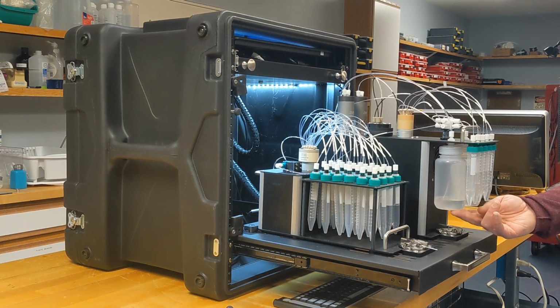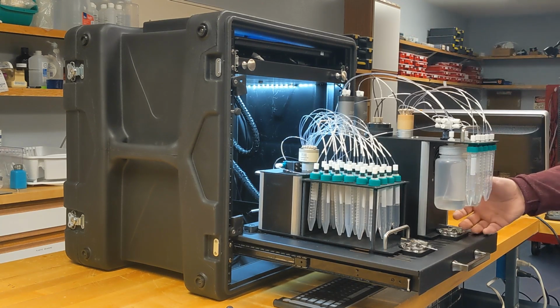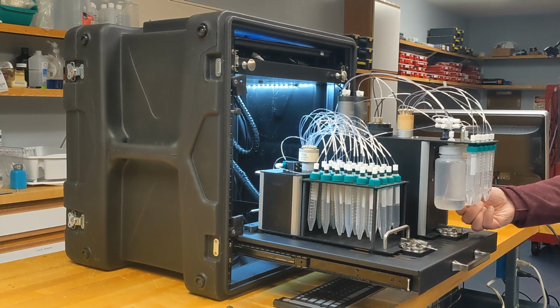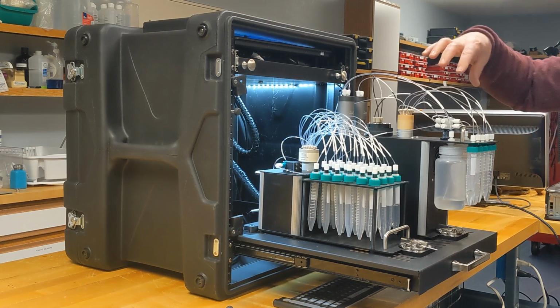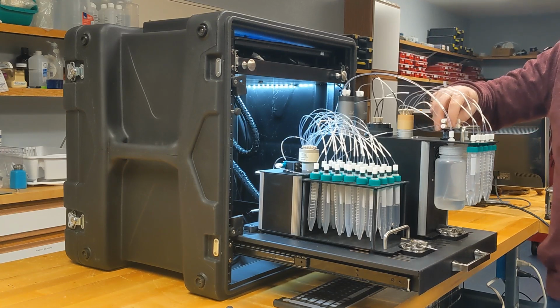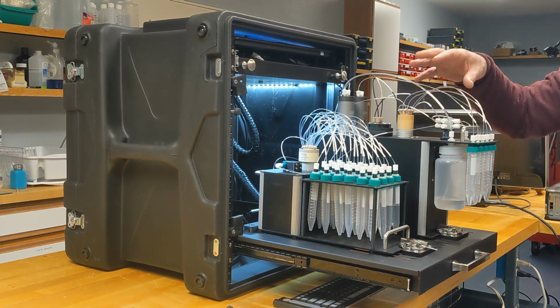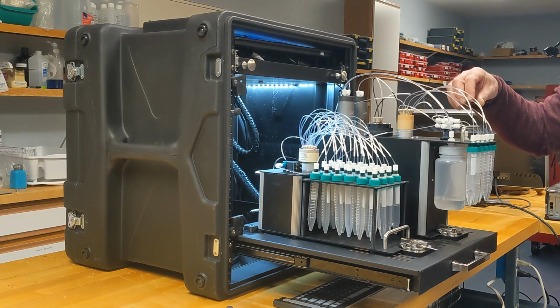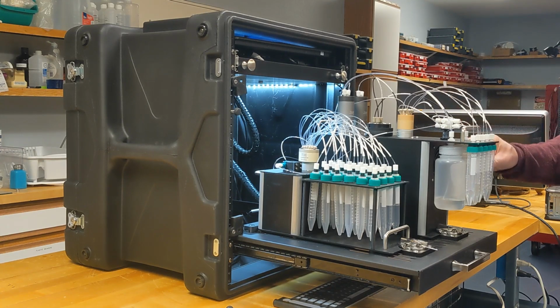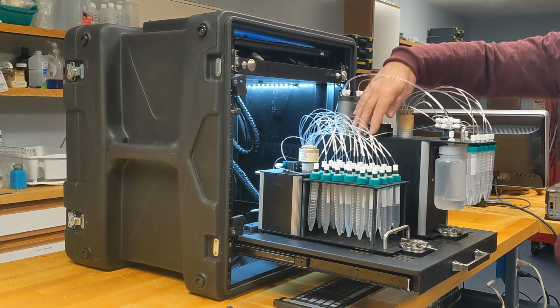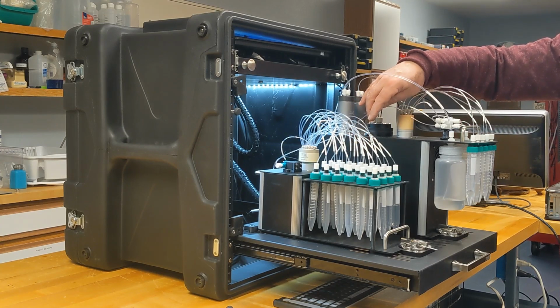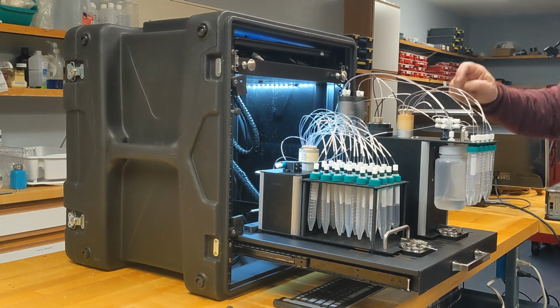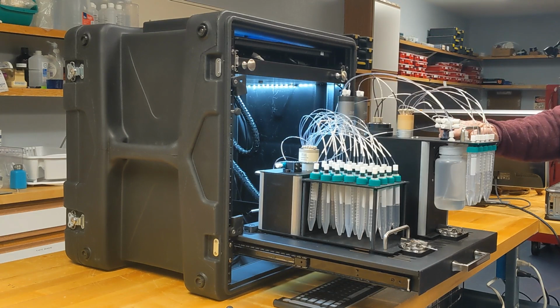Behind that, there's the carrier stream. This is the stream that carries the fluid through the analyzer, and a waste bottle. Behind that is a stack of fittings here which control all the different waste ports and send the solutions from those waste ports down into the carrier stream, and also manage the flow of sample from the multi-sampler into a holding coil, which is here at the bottom, and it's from this holding coil that you draw the sample.